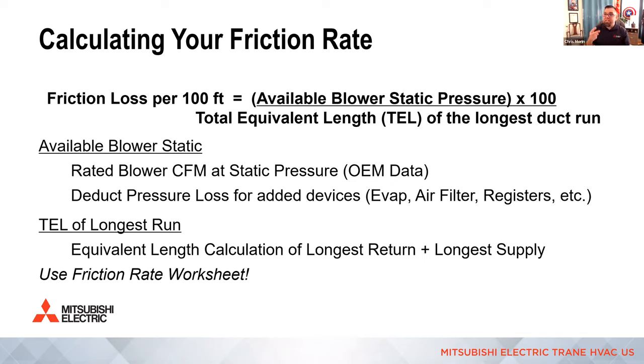There are two pieces of information you need in order to calculate the right friction loss. The first one is how much available blower static pressure you have. So you start with something for the air handler and you deduct these devices that are in the way. And then the total equivalent length and actual feet of the longest duct run. Because if you can get air to the longest run, we have balancing dampers to then balance the rest of the system for the rest of the house, right? So those are the two pieces of information, and I'm going to walk you through that.